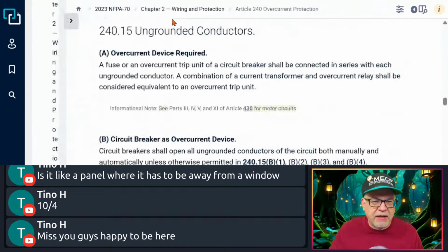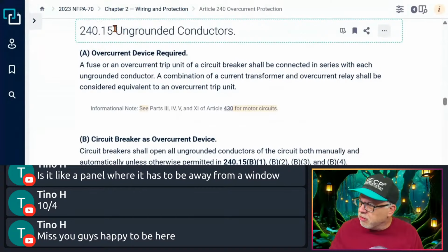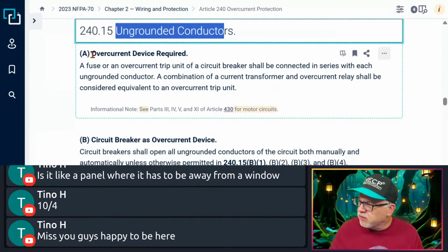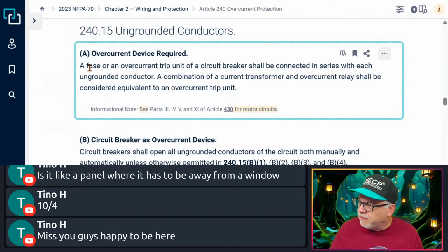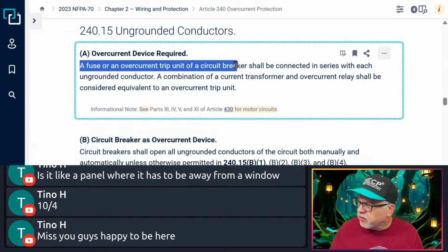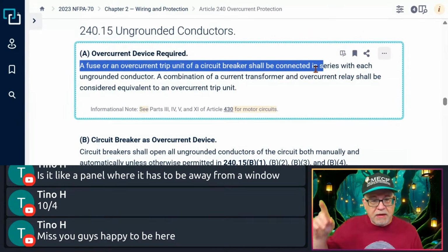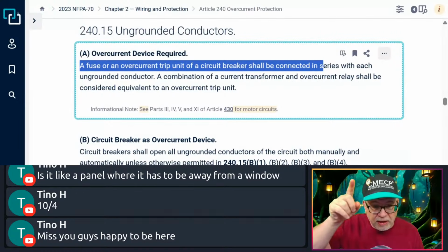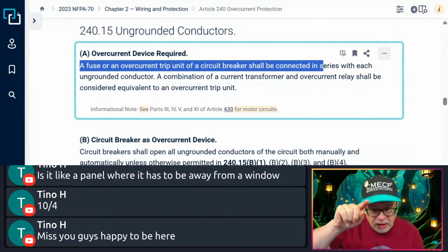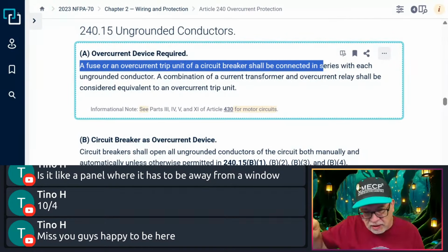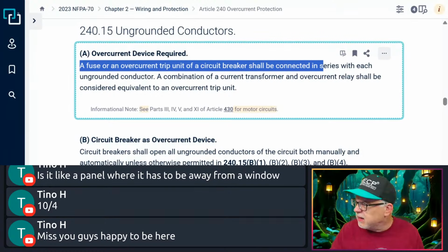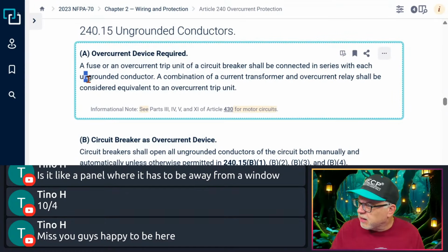All right, so we're in 240.15. We're talking ungrounded conductors, right? And here's where it says overcurrent device required. It says a fuse or an overcurrent trip unit of a circuit breaker shall be connected in series. Means it's coming in series, right? So you've got the black conductor and you've got the fuse. It's running through it in series, and then it's going out to the load. That's in series, okay? So in series with each ungrounded conductor.